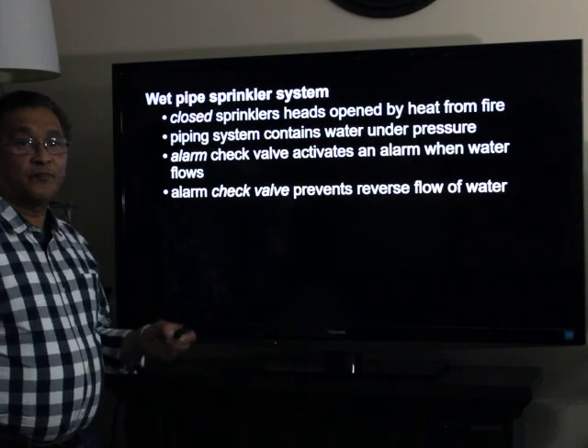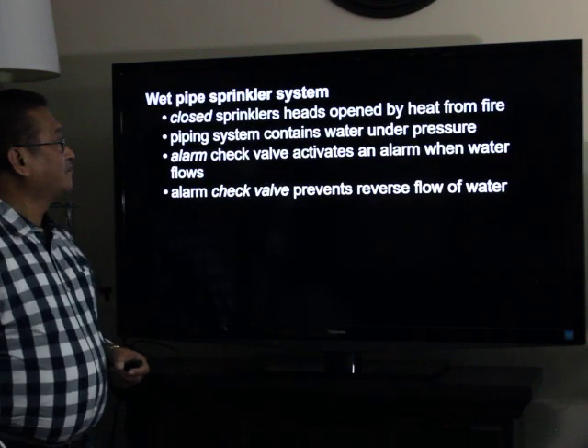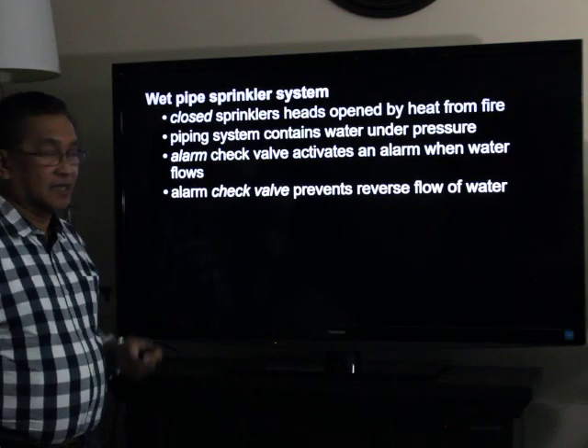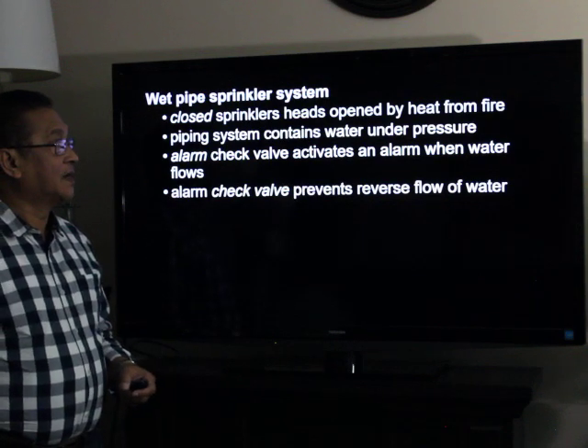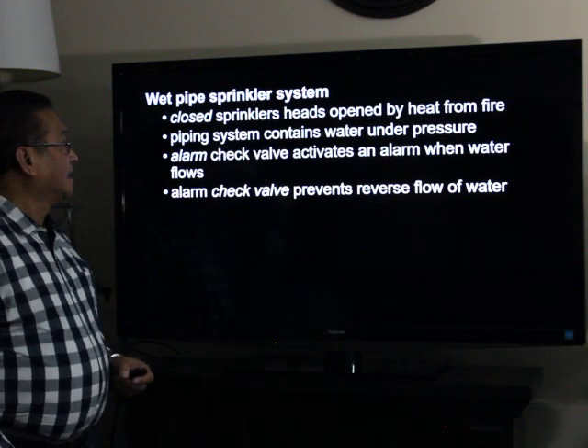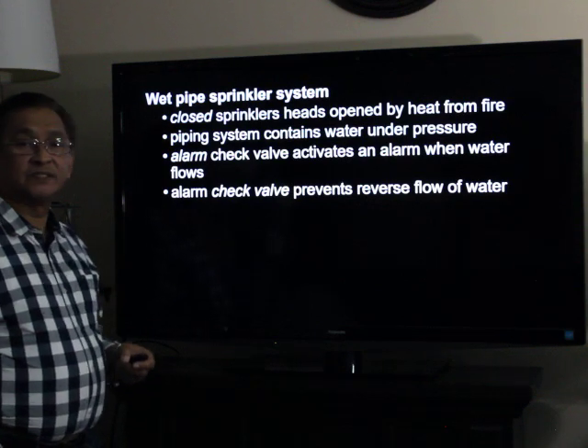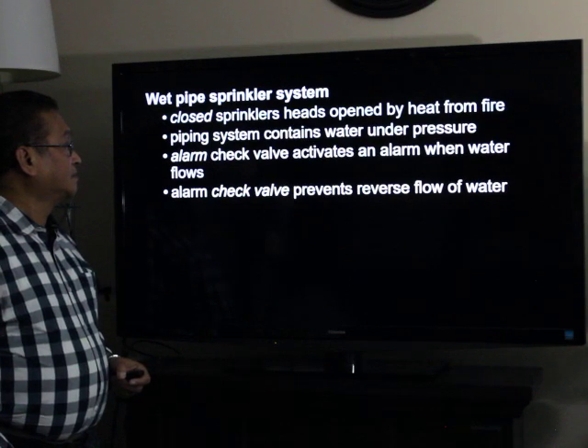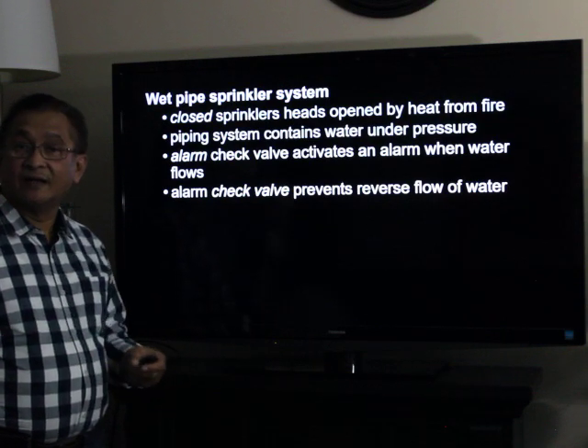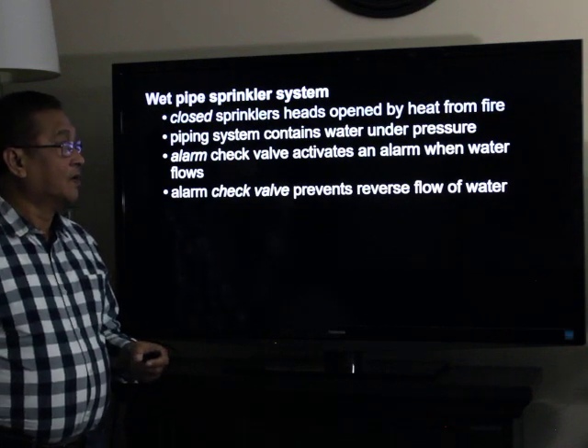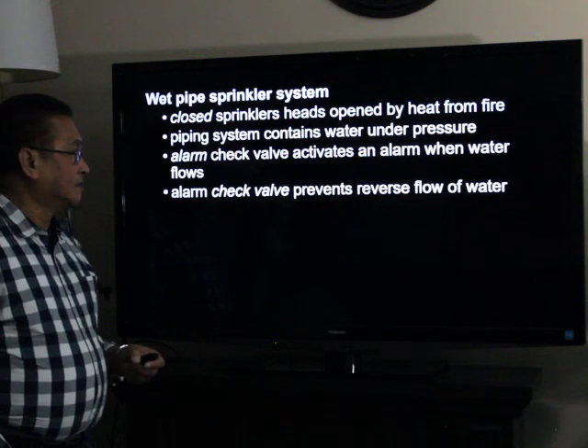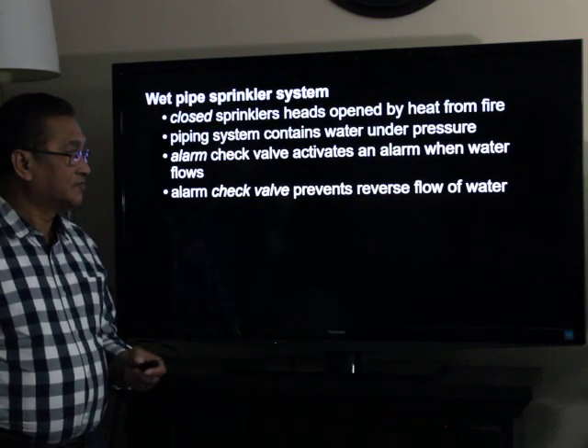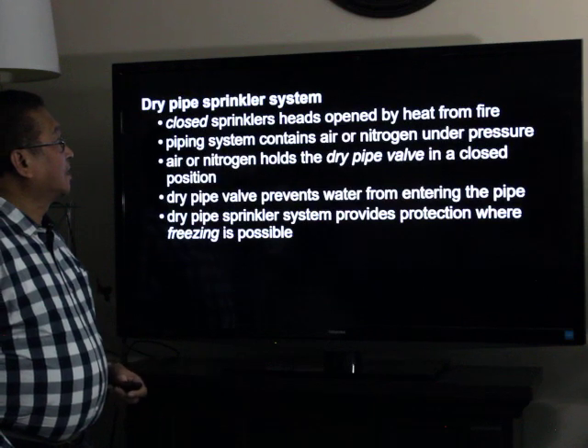For a wet pipe sprinkler system, it is composed of closed heads which are opened by heat from the fire. The piping system contains water under pressure. The alarm check valve activates an alarm when water flows, and the alarm check valve prevents the reverse flow of water.